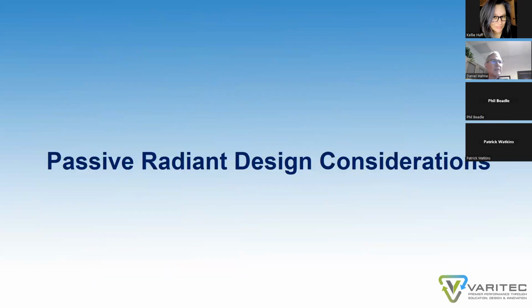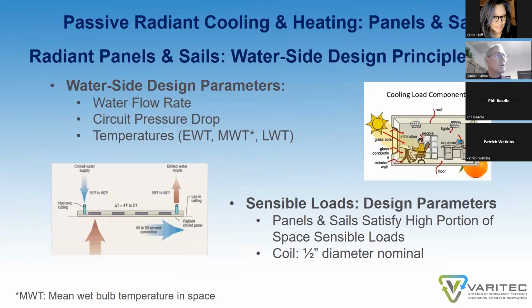So, what are some passive radiant design considerations? Well, let's look at the water side design factors. Now that we've looked at some of the preliminary air side factors, we need to ask ourselves the question about the water side. We need to determine what the water flow rate is to be to each zone. We need to determine the pressure drop that is available. We need to determine the temperatures of the water and of the room being served by the system. So what is the entering water temperature and the leaving water temperature? The sensible load design parameters have to be done, again as a reminder, in relation to how much sensible cooling is achieved by the ventilation or outside air factor. And then, of course, the sails and panels are designed accordingly in respect of that.